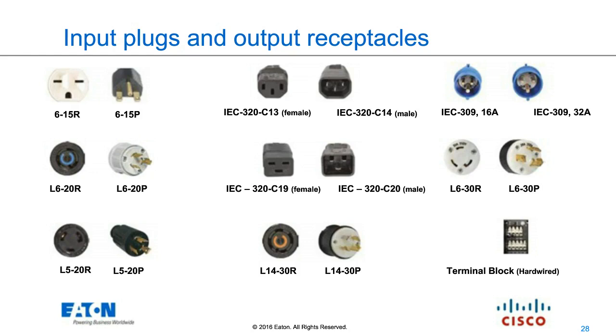And so this slide here is probably a better representation of what we're going to see in a converged blade type of scenario. These are going to be much higher density receptacles. Yeah, and typically, just to jump in here, you'll find that most blade architectures will have a C19, C20 combination on the rear. So we would expect, in the Cisco UCS environment, for example, we have 4 C20s on the back. So we expect to use a C19, C20 jumper cable to go to the PDU. Similarly, HP have 6 C20s, if I remember correctly, and I think the Dell chassis also has 6 C20s.